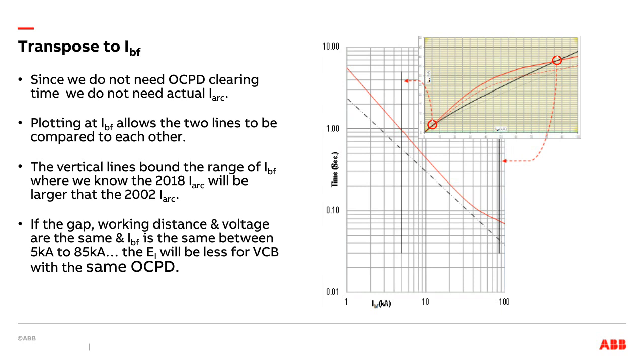Notice these 2 vertical lines. What those 2 lines represent on this graph is this region and that region. The region where the new arcing current would be higher than the old arcing current, based on comparing the 2 studies. What you know about this region here is that your protection is going to be equally fast or faster. It is not going to be slower.